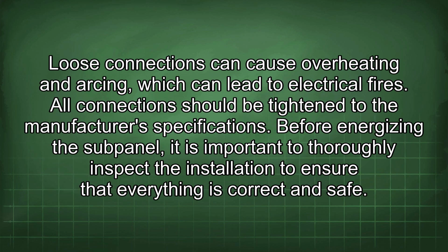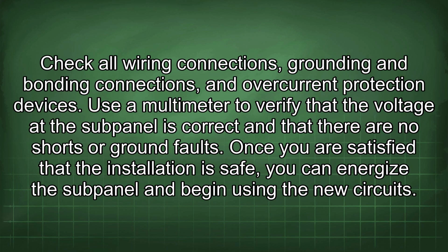Loose connections can cause overheating and arcing, which can lead to electrical fires. All connections should be tightened to the manufacturer's specifications. Before energizing the subpanel, it is important to thoroughly inspect the installation to ensure that everything is correct and safe. Check all wiring connections, grounding and bonding connections, and overcurrent protection devices. Use a multimeter to verify that the voltage at the subpanel is correct and that there are no shorts or ground faults. Once you are satisfied that the installation is safe, you can energize the subpanel and begin using the new circuits.